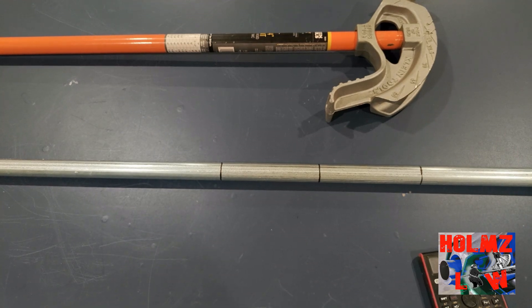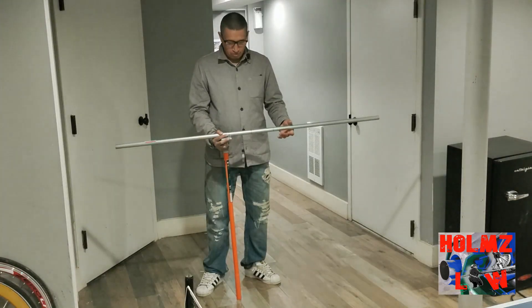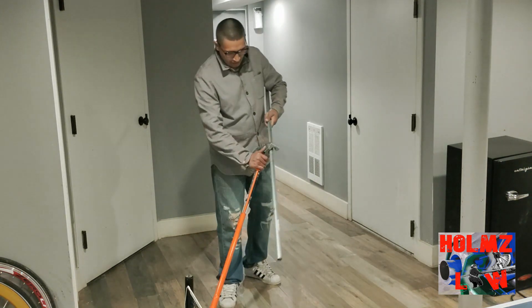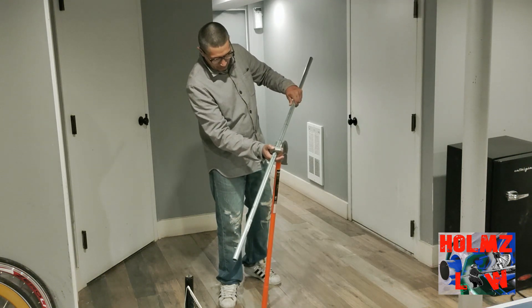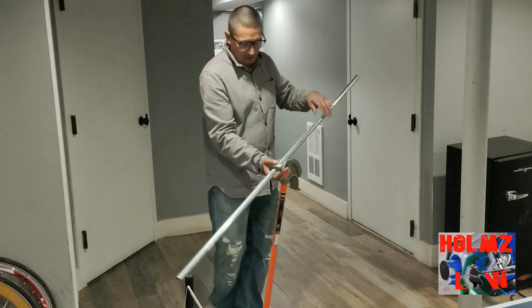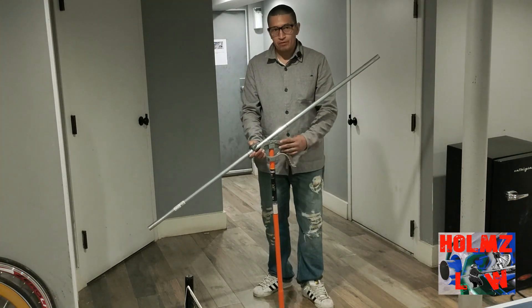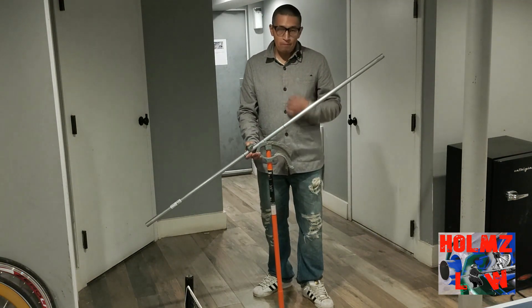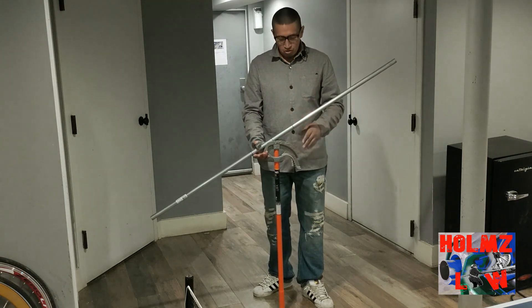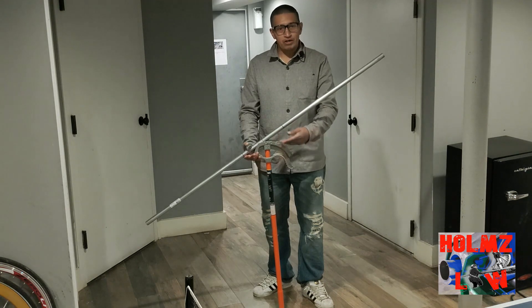Here I am with the bender and my conduit already laid out — center bend and two side bends marked. Just like any other three-point saddle, go ahead and place it on the notch for the center bend. If you can't see, it's right on the notch — or the teardrop if it's a Klein bender. We're going to bend it to 22.5 degrees. The trick is you don't have an 11-degree mark on your bender, but you do have a 10-degree mark. Anytime you don't have the exact degree mark, you can judge where it's going to be and tweak it as you go.